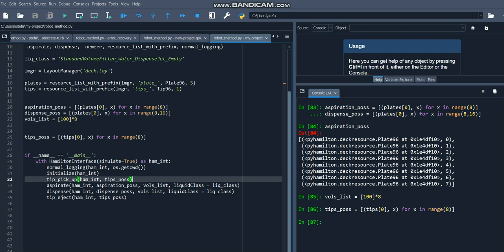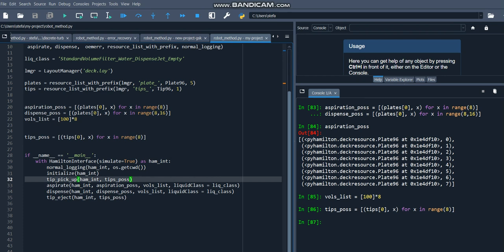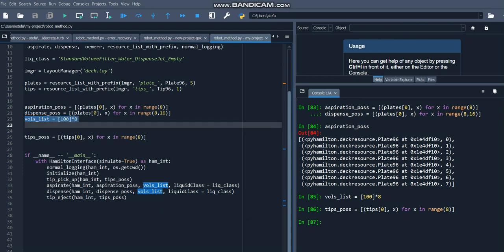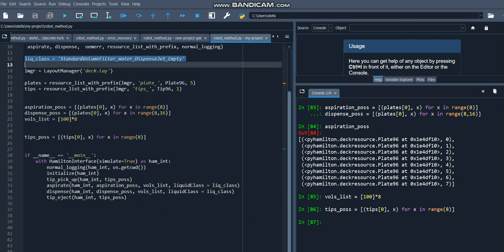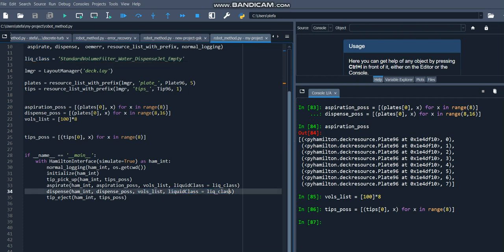Next, we're picking up the tips that we've specified in the tips positions variable, very simple. And then we are aspirating from the aspiration positions with the volumes that we've specified here, and the liquid class that we've specified up here. And then we're dispensing with those same volumes and same liquid class with the dispense positions. So that will be in the second column of the plate.